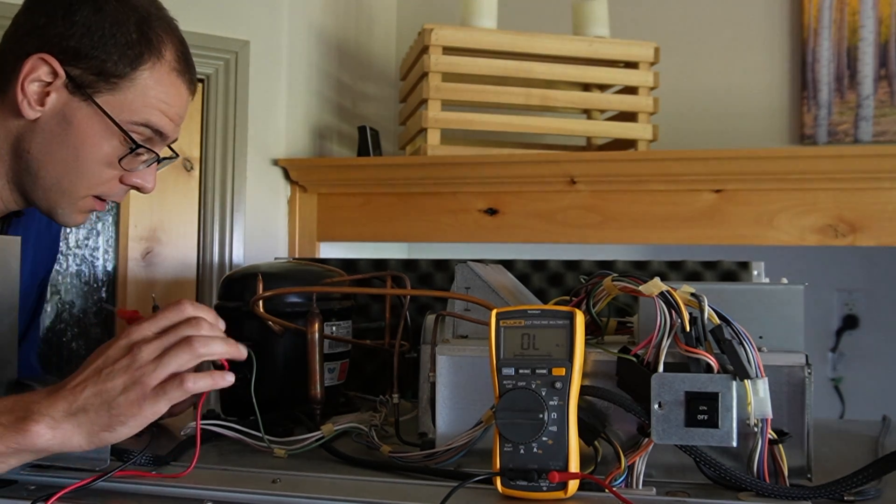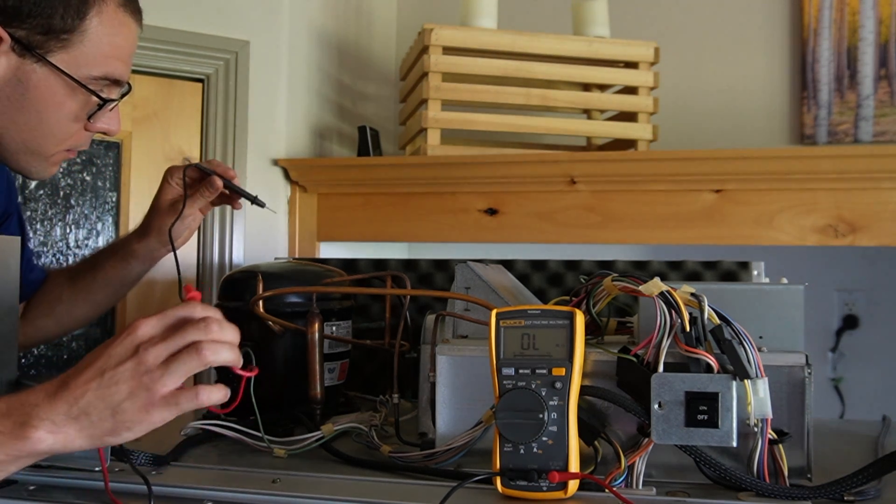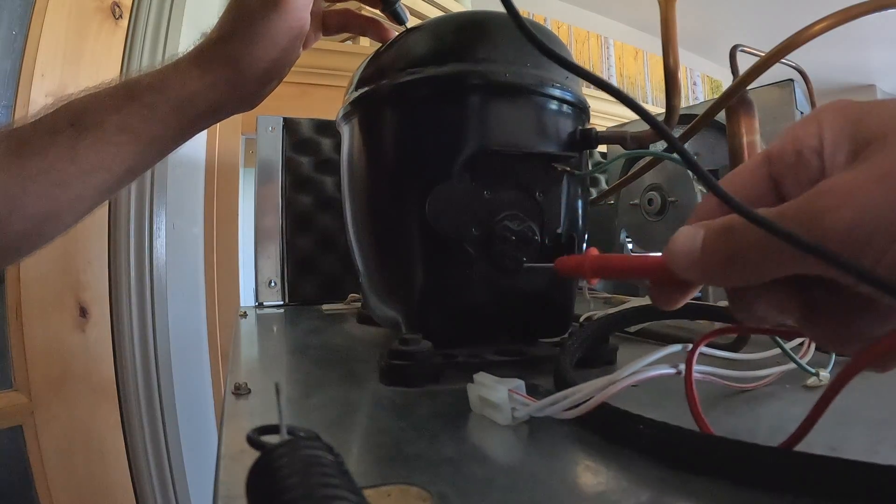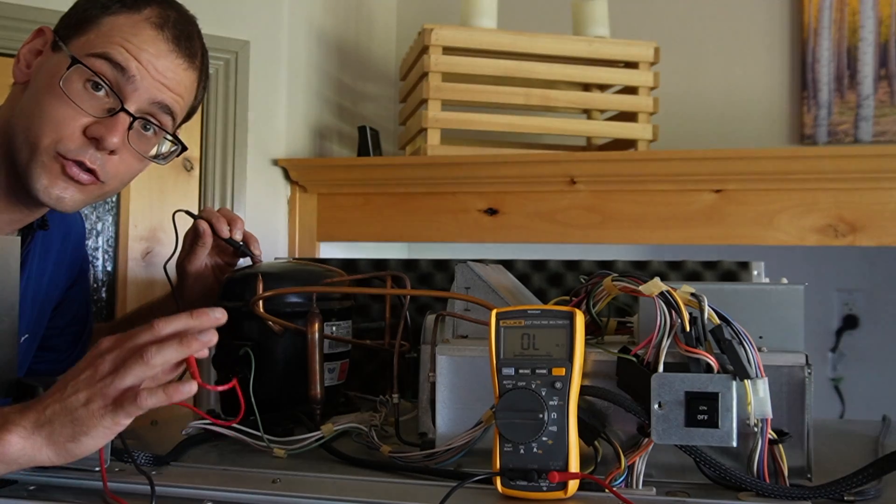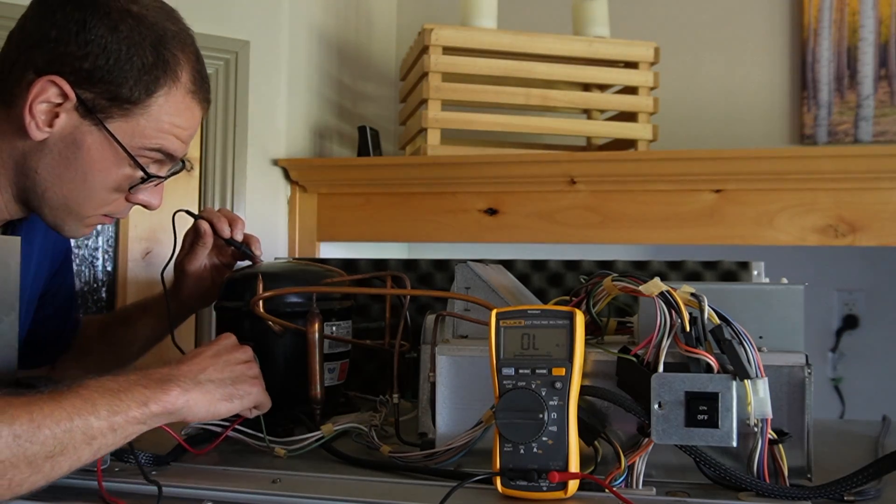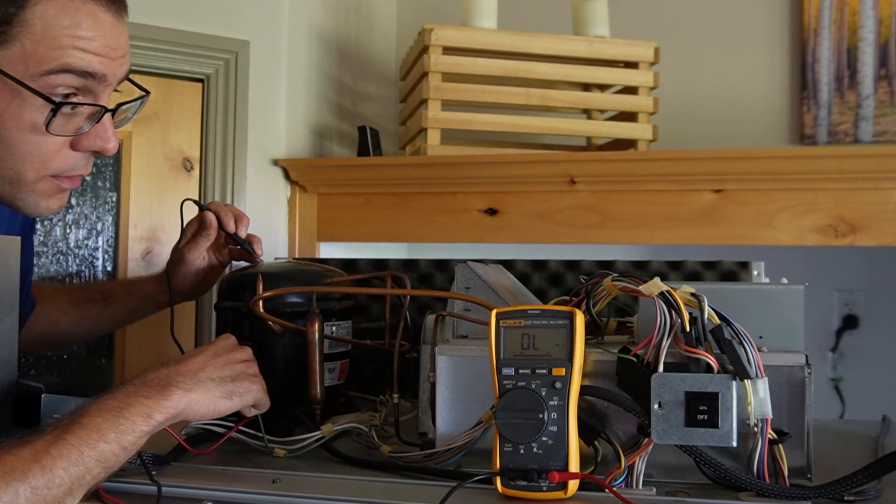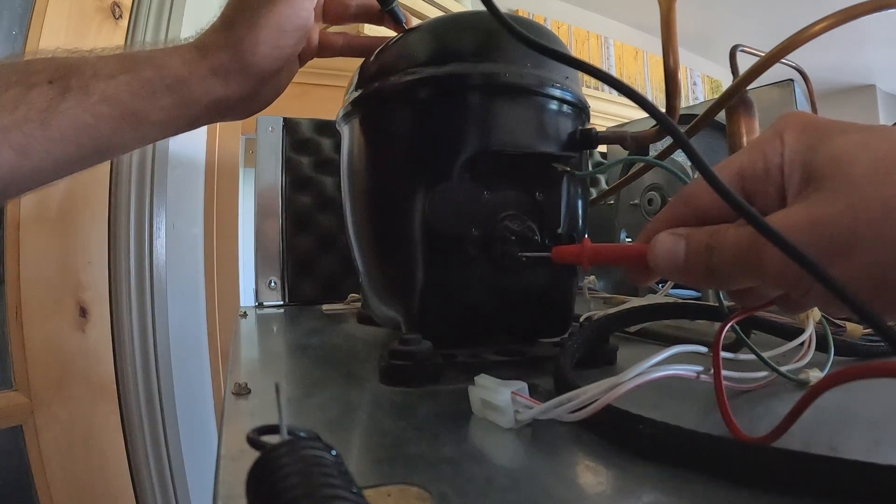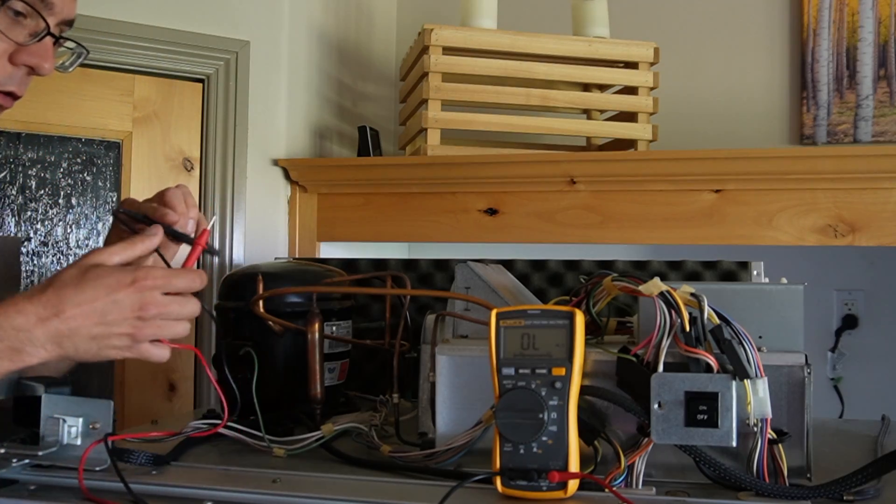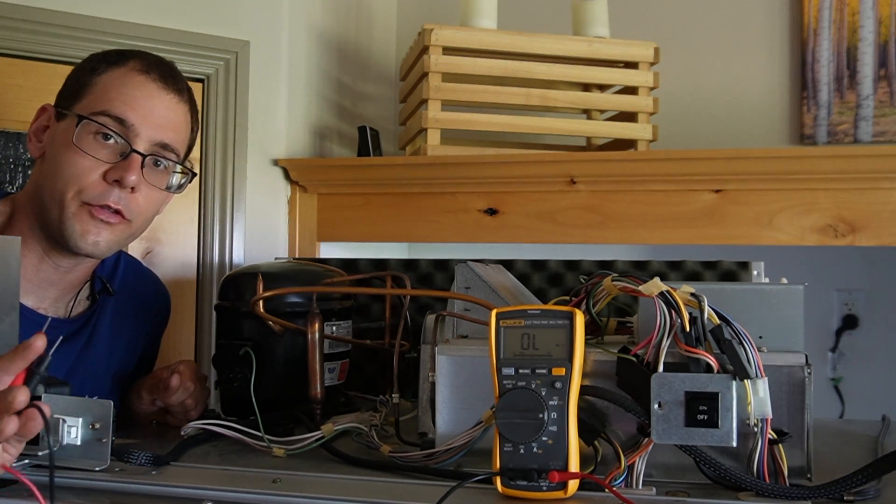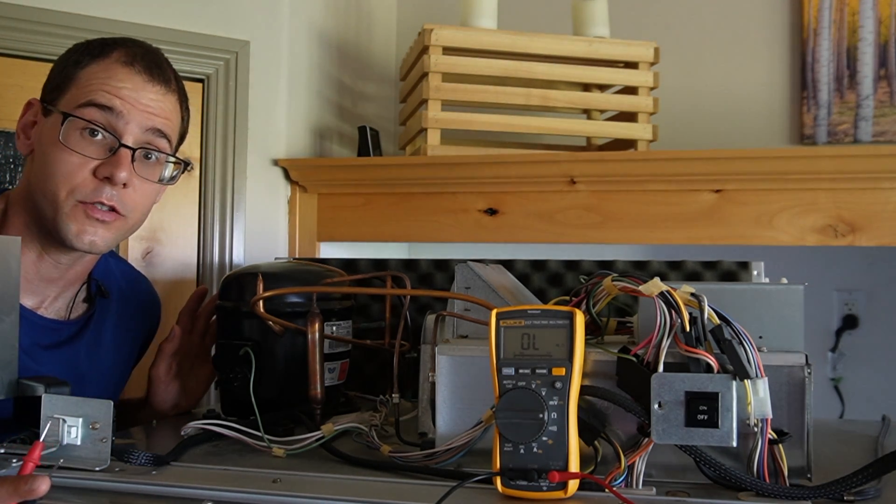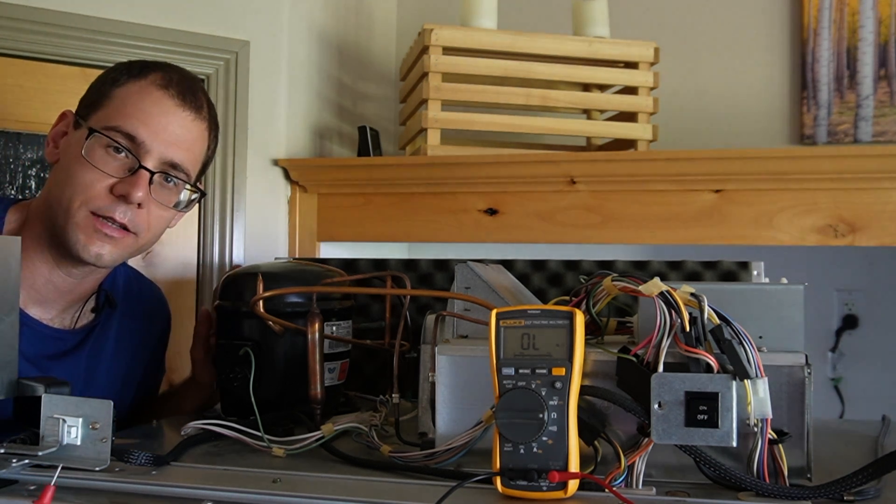We should do one more check to verify that. I'm going to put one probe on the body of the compressor and one probe onto each of these three leads to make sure there's no shorts to ground. We want no connection between any of these three leads and ground. On the left it's reading OL, that's good, that means it's open. On the bottom, same thing. On the right side, same thing. This is very good news. It looks like our compressor is okay. The windings inside are okay and the resistance values are what they should be. So this thing likely will work, and we're going to try that in the next step.